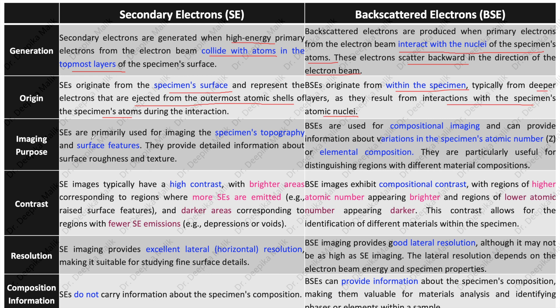Secondary electrons are primarily used for imaging the specimen's topography and surface features, providing detailed information about surface roughness and texture. Backscattered electrons are used for compositional imaging, providing information about variations in the specimen's atomic number or elemental composition, and are particularly useful for distinguishing regions with different material compositions.